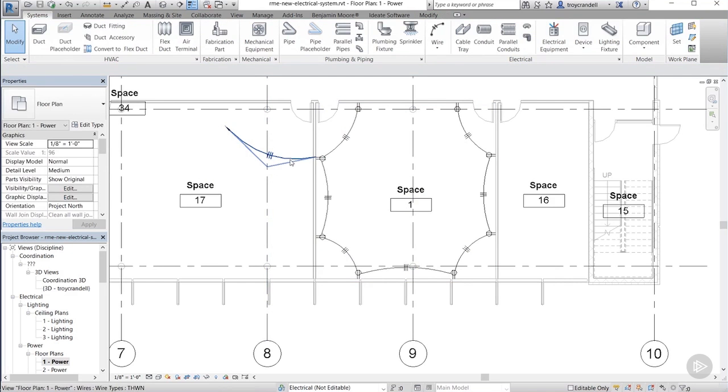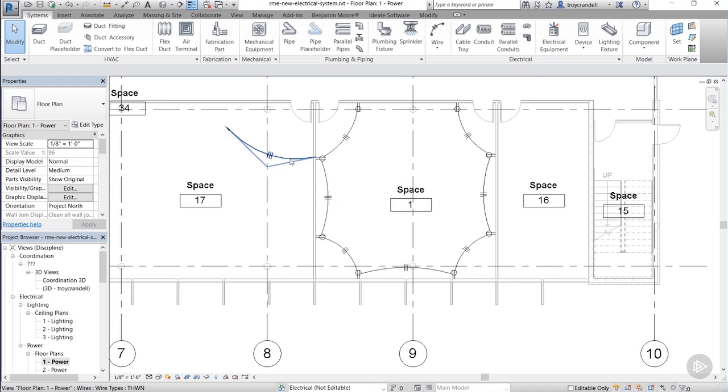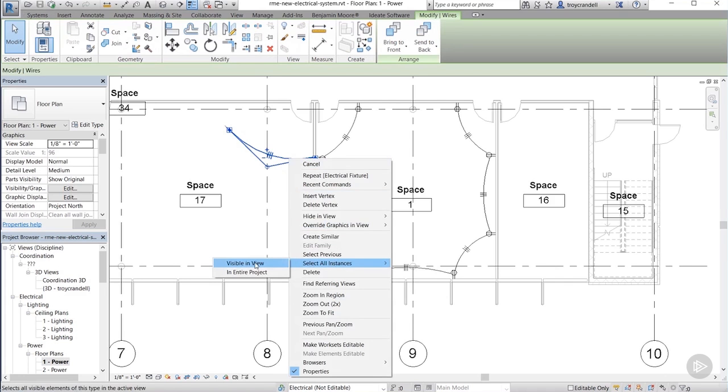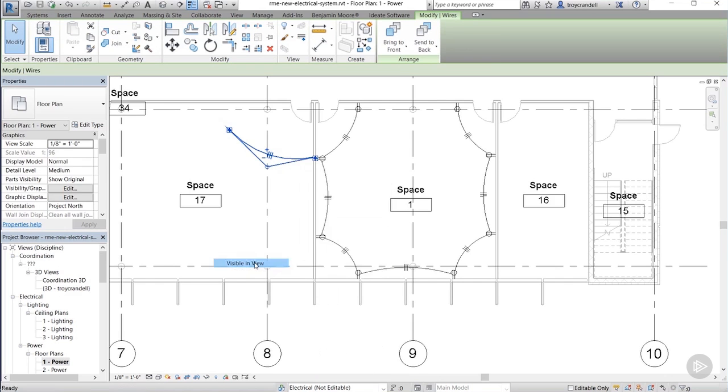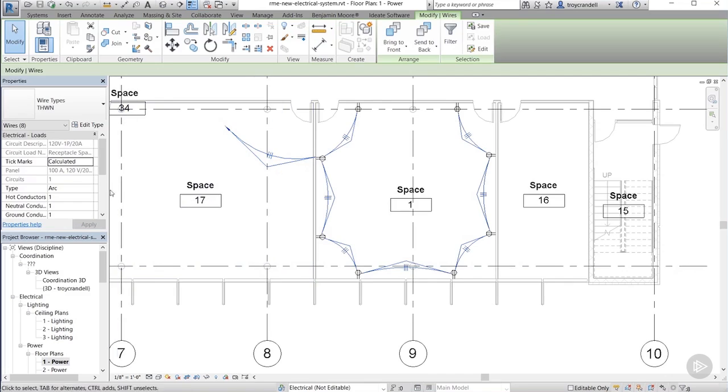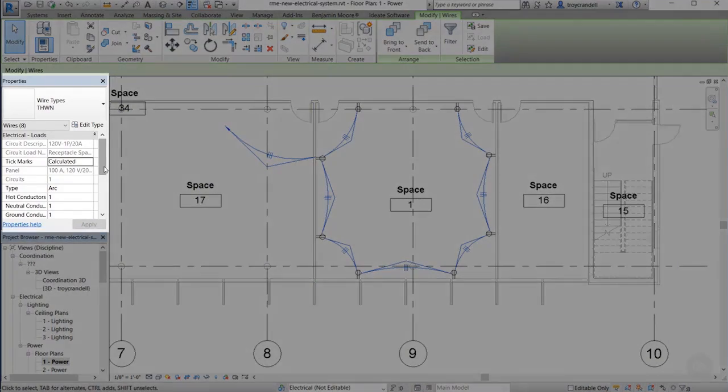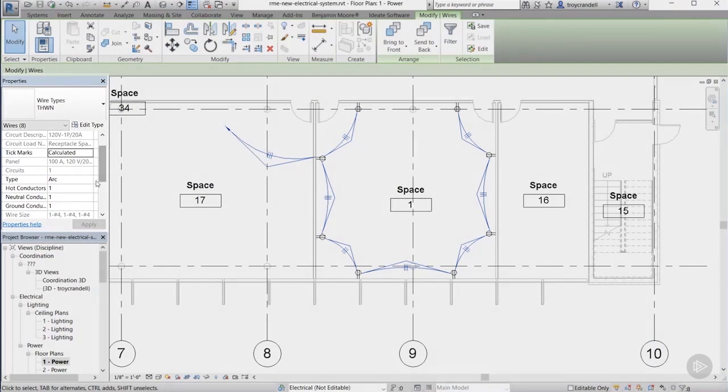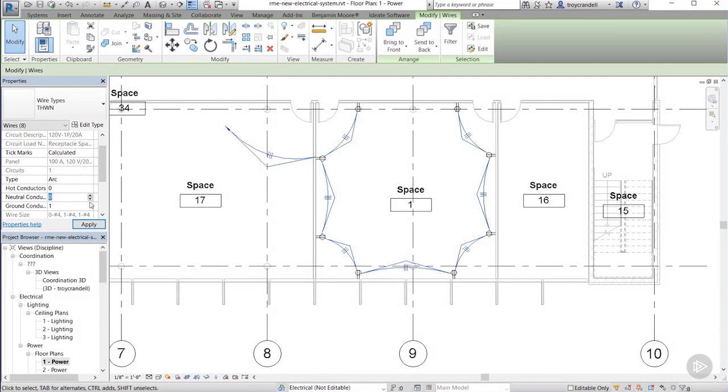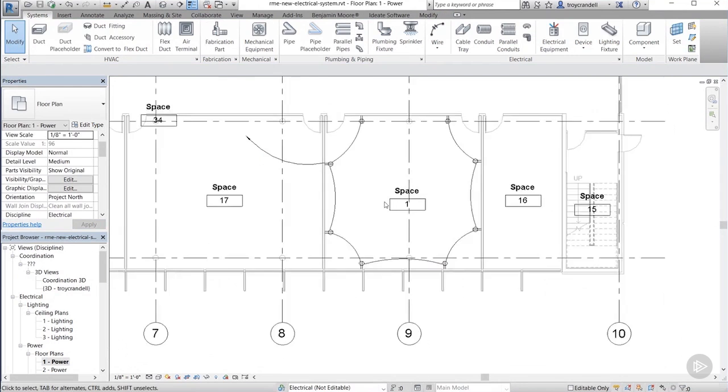Now, Revit automatically put these little tick marks on the wire, and I know that my standard in our office doesn't call for those tick marks, so there's a pretty easy way to go about removing those. If you select the wire and then right-click the wire, in the right-click menu, just move down to the Select All Instances, and we're going to choose Select All Instances in View. That will then select all of the wiring in this particular view. With all of them selected, I can go over to the Properties palette and remove those tick marks by setting each one of them to zero. And voila, they are gone.